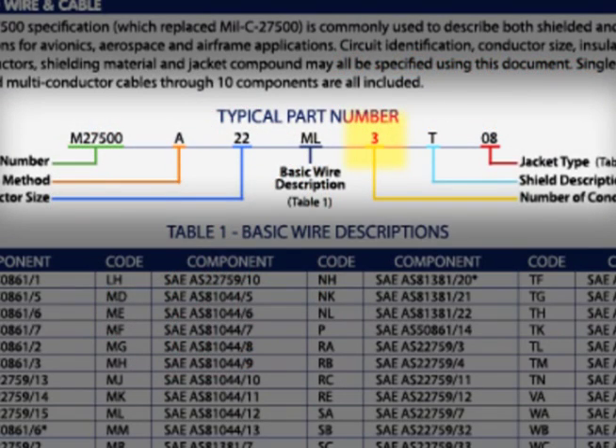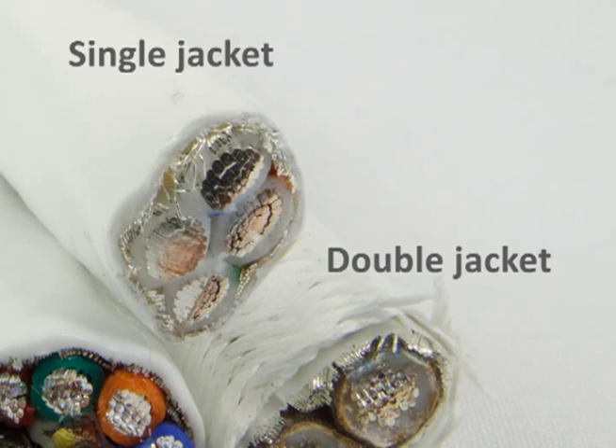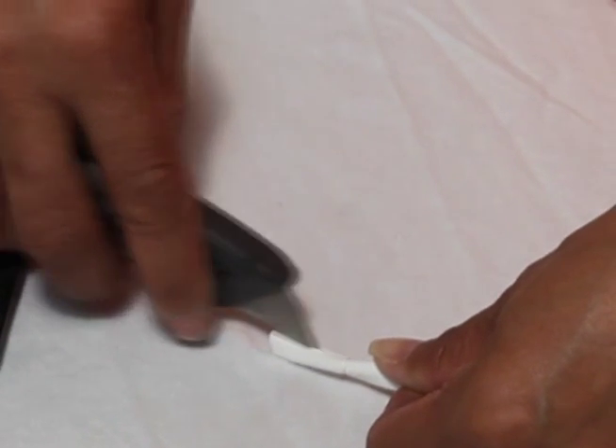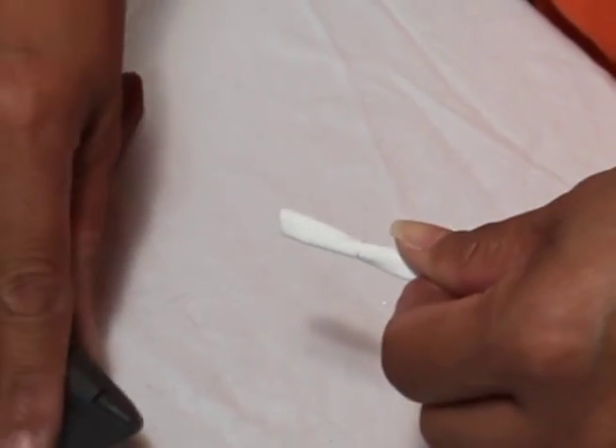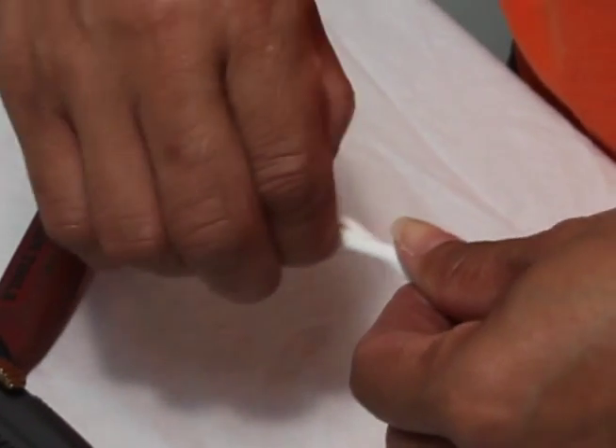Jacketing is specified by a two-digit code at the end of the M27500 part number. Cables may have no jacket, a single jacket, or a double jacket. If jacketing is applied, it must be easily removable from the rest of the cable.